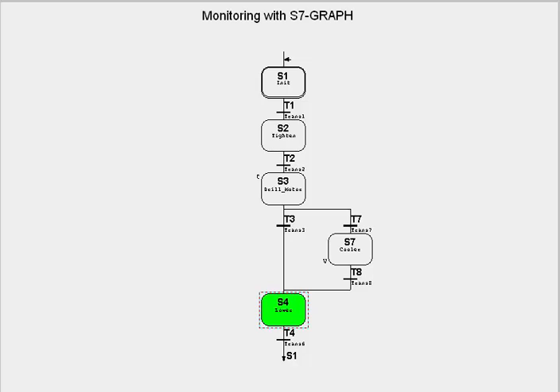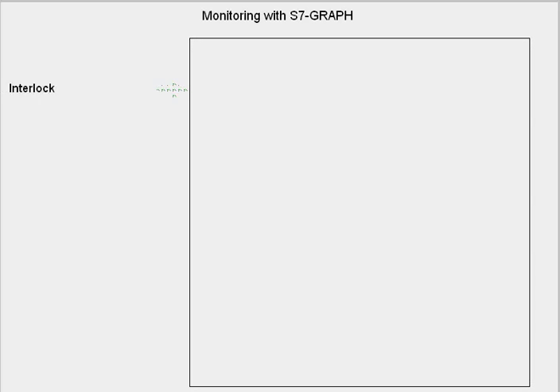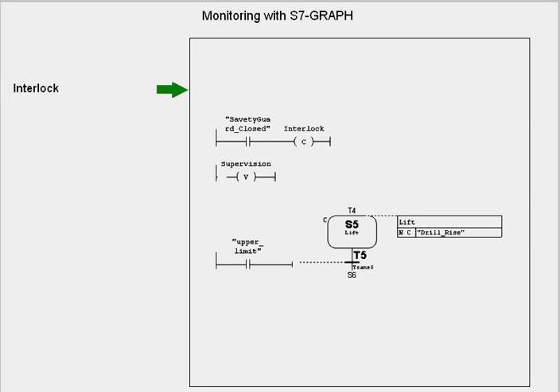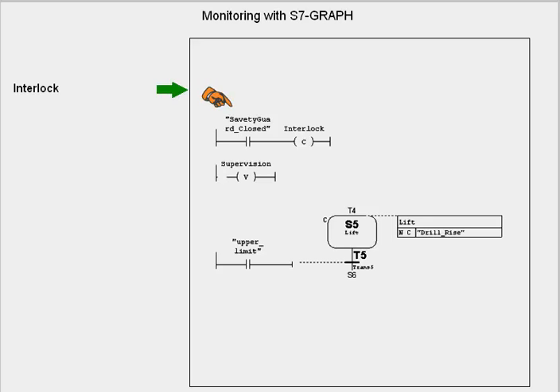The S7 Graph knows two types of error monitoring, the interlock and the supervision. The interlock is a programmable condition which affects the running of individual actions of the sequence. If the interlock condition is not fulfilled, in other words, there is an error, an interlock fault is announced, and all actions linked to the interlock are blocked.